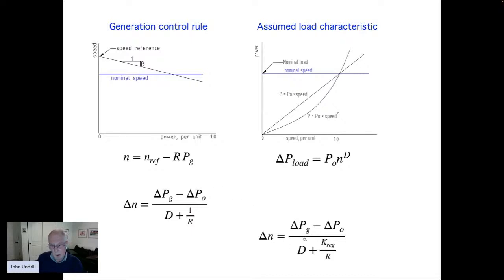In the last 20 years or so, we've recognized that not every generator connected to the system contributes to control. There are a lot of generators that prefer to run at maximum power and not be maneuvering as the load maneuvers. Well, by balance, the generation must balance the load. But every generator doesn't need to contribute to balancing generation with the load. And typically, about 30% of the generators in a typical power system will maneuver and contribute to the solution of this equation. And the other 70% will operate at fixed power.